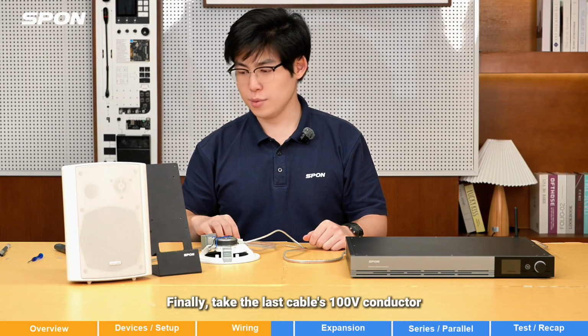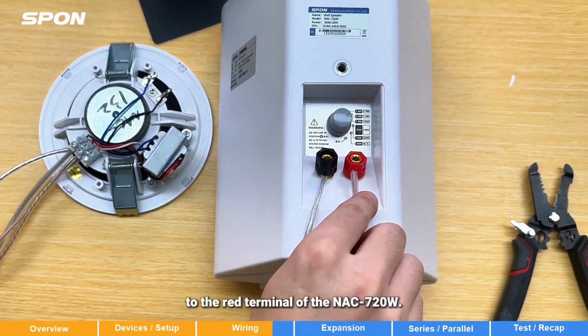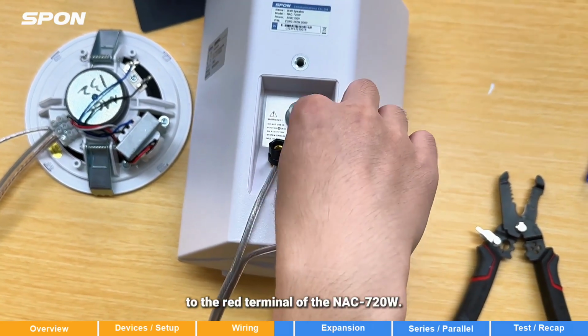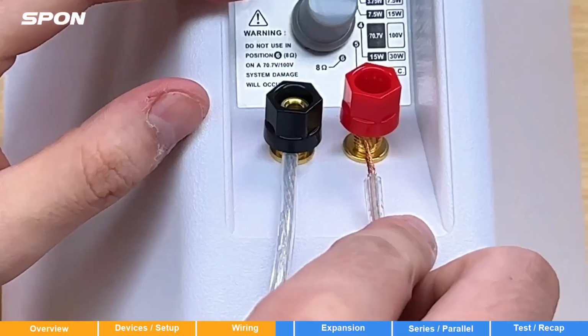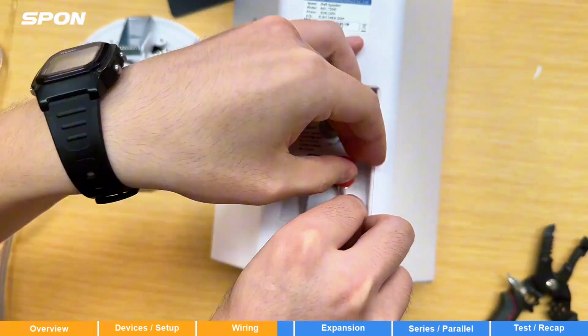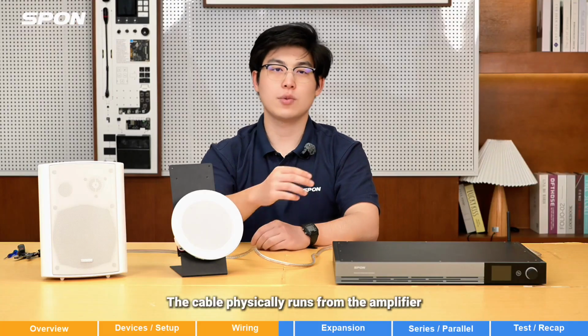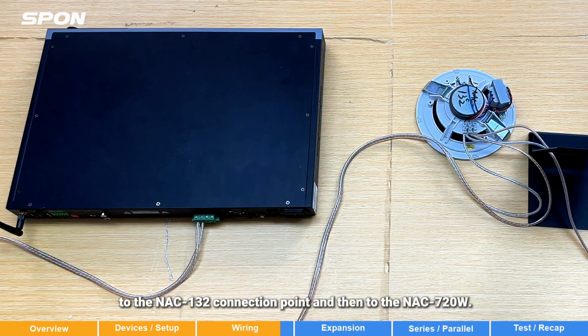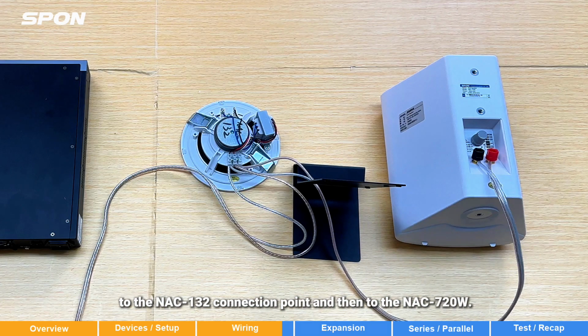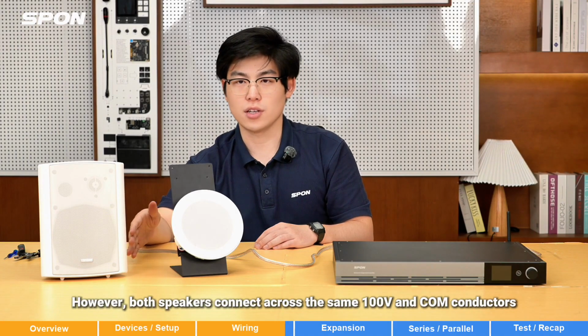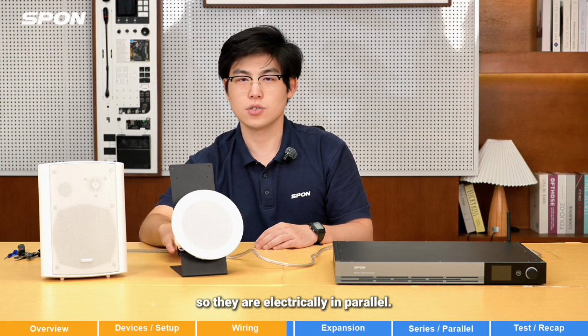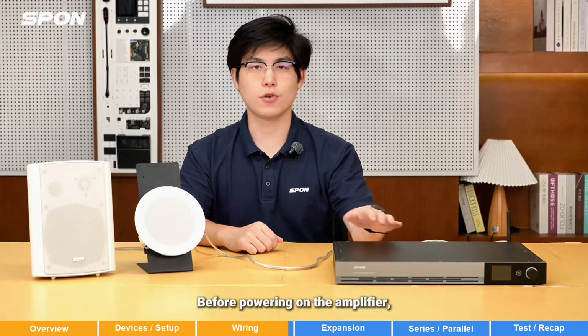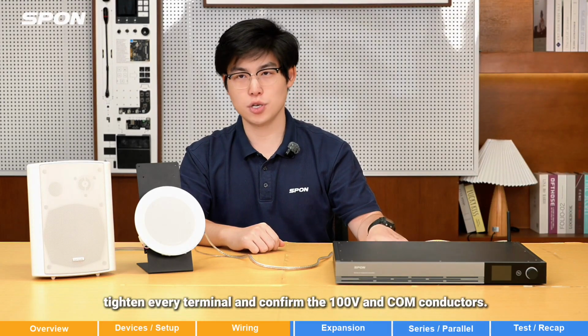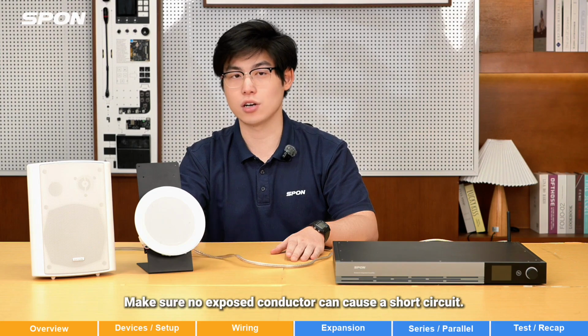Finally, connect the last cable of the 100 volt to the red terminal of the NAC-720W. The cable physically runs from the amplifier to the NAC-132 connection point and then to the NAC-720W. However, both speakers are connected across the same 100 volt and COM, so they are electrically in parallel. Before powering on the amplifier, tighten every terminal, confirm the 100 volt and COM conductors, and make sure no exposed conductor can cause a short circuit.